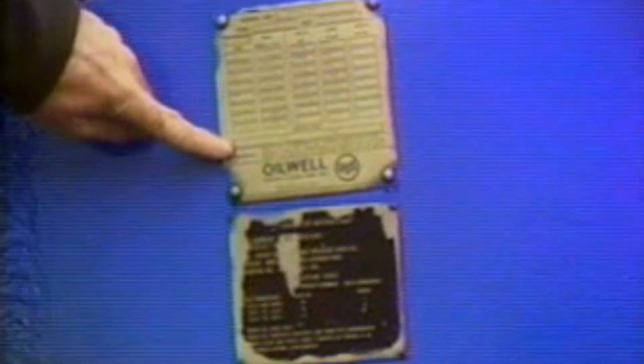Close the mud trap and crankcase drain and fill the crankcase with a proper lubricant, normally AGMA number 5 or 7 extreme pressure heavy-duty gear lubricant. There's a plate on the side of the pump which tells you how much lubricant and what type is recommended for your pump. These plates may be outdated though, so always follow the instructions of the senior engineer for your area.